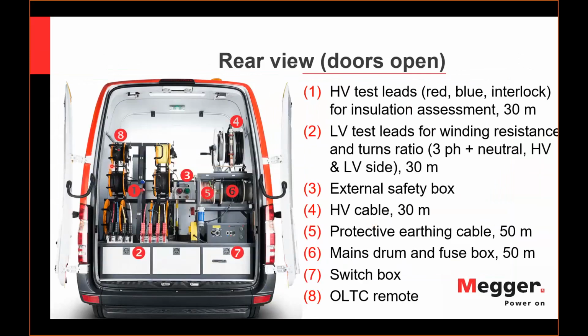In the back of the vehicle, all cables are collected on cable reels. They are typically available in two lengths: 50 meters for power supply and protective ground, these are drums 5 and 6, and measurement leads that are normally 30 meters. They are there for the high voltage cable up to 12 kilovolt, red and blue lead, interlock lead, lead for the external safety lights, just to indicate the presence of voltage also outside of the vehicle, to give a warning signal to a second colleague who would be working outside and connecting the leads, and low voltage test leads that are connected to both sides of the transformer at the same time. So all three phases plus neutral on the H and X side.